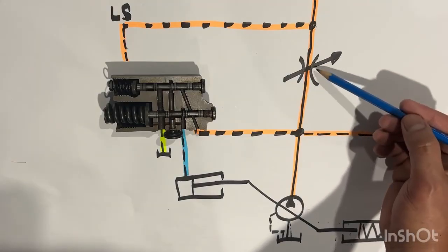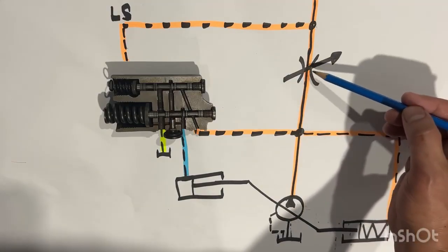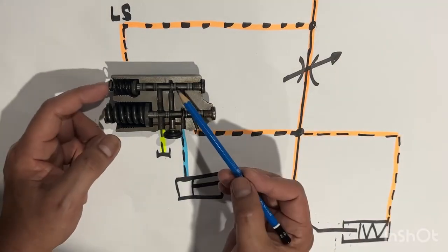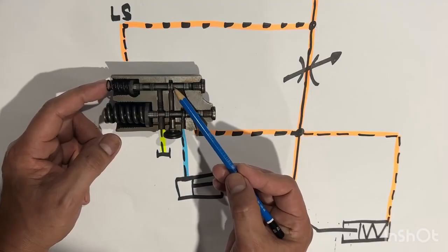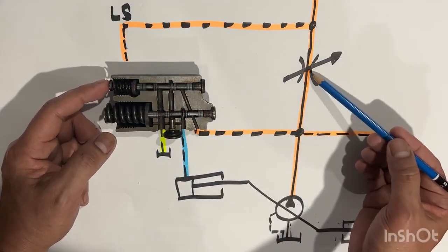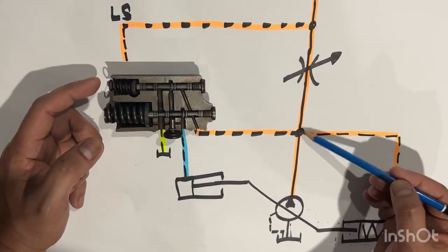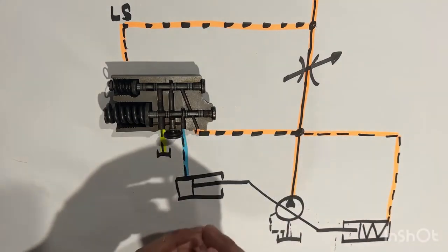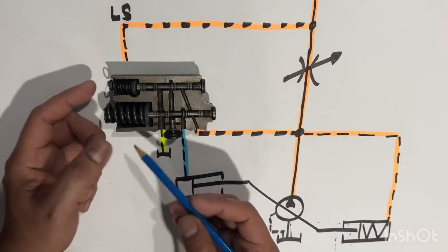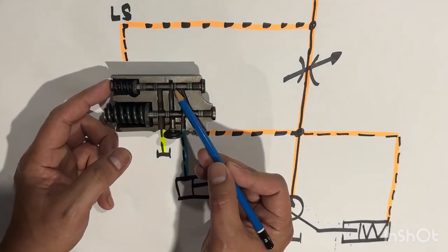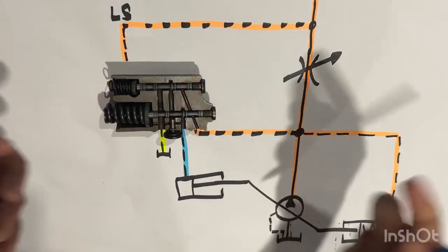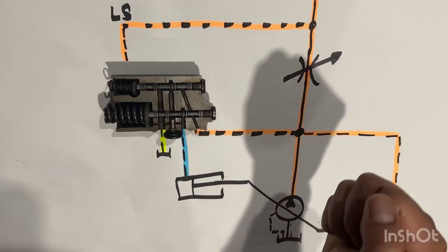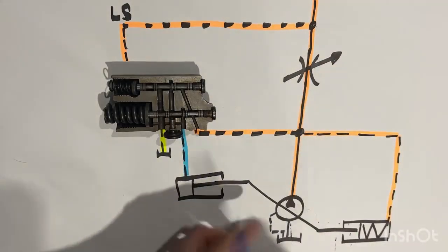close the control valve, if you decrease the area of the control valve, the delta P here will rise. What happened? This spool will move to the left. If the control valve opening is wide, the delta P here will decrease, because according to Bernoulli's equation, once the area is increased, the delta P is decreased. So meaning, if that happens, this spool here will move to the right, and then it will max stroke, which is correct, because the control valve is opening wide, so you need more flow. So meaning you need max stroke.